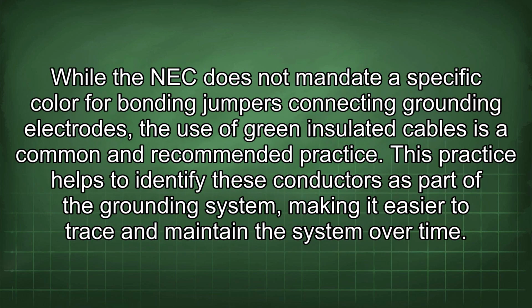While the NEC does not mandate a specific color for bonding jumpers connecting grounding electrodes, the use of green insulated cables is a common and recommended practice. This practice helps to identify these conductors as part of the grounding system, making it easier to trace and maintain the system over time.